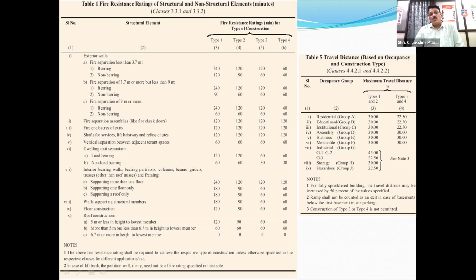Fire doors also need to be provided in all high-rise buildings for all the exits, and wherever they are prescribed, like cellars enclosing the lift and staircase lobbies. So there are various places where the fire doors need to be provided to ensure that 2 hour compartmentation is maintained. And we have got travel distance also prescribed in the National Building Code. What should be the farthest distance that any person should travel before arriving at an exit?